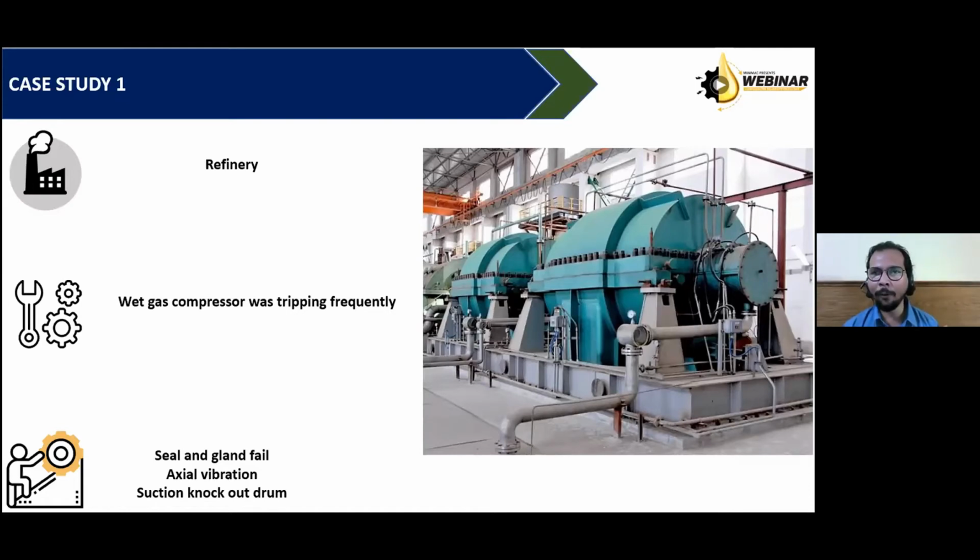Later on, we concluded how it was happening, and we did nothing but change the seal type, because that oil was eating away the seal. The seal used to touch the rotating component to avoid any crossing of gas into the lubricating chamber. Those seals were getting damaged, and after that, the lubricating oil was getting contaminated. We will see one more case.